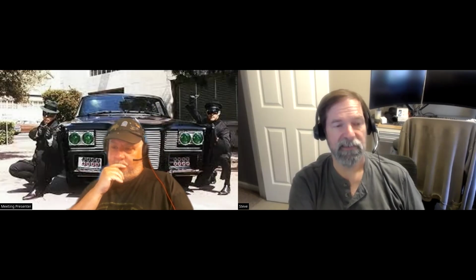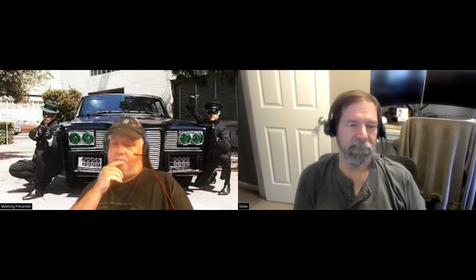And I'm going through here, and every rack actually has 6 individual breakers in it. And we're just flipping these little tiny breakers, and you can do about 4 racks before you've got to get out of the room. It was 140 degrees in there. Wow. And that was after they had been running fans in the doorways for an hour, hour and a half at that point. It was all sorts of fun.